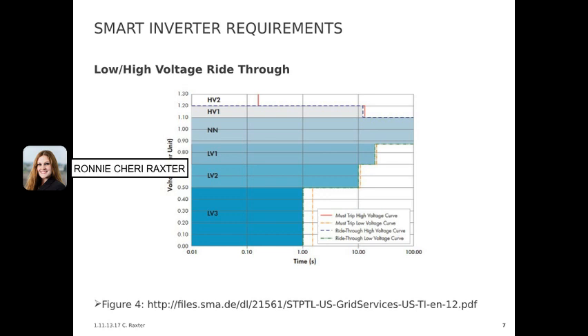The second requirement mentioned was the low-high voltage ride-through setting. Now this has to be activated, just like the anti-islanding. Ride-through is referring to the ability of the DER to stay connected during a high or low voltage event for a predetermined voltage percent and duration of time. For Rule 21, the Phase 1 change, the high voltage percent hasn't changed, but the time to disconnect was extended. On the low voltage side, the low voltage percent and time to disconnect have both been altered.